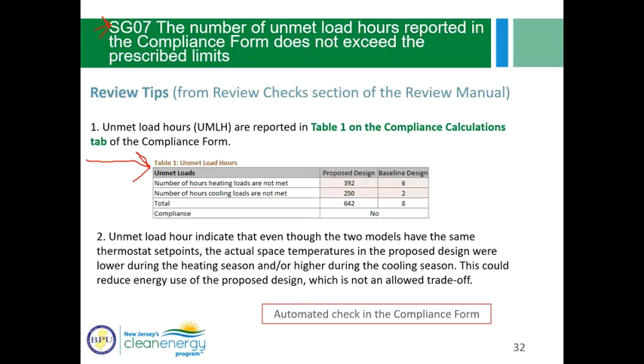So in our example here, we can see that there are 642 unmet load hours in the proposed, and that means that there are 642 hours where less heating and cooling is being provided, or potentially being provided, in the proposed model. The space temperatures in the case of heating are lower, or the space temperatures in the case of cooling are higher than the baseline, because the schedules need to remain constant between the two models. And that's not an allowed trade-off. You can't get credit for reducing occupant comfort in the proposed model. So that's why this one is very important. And this check is automated in the compliance form.